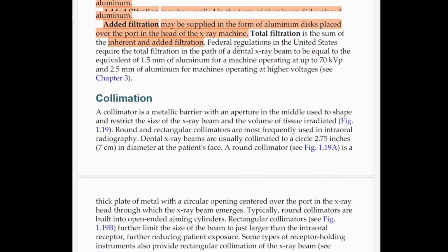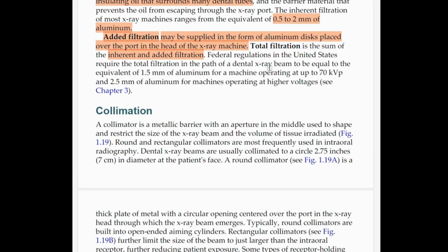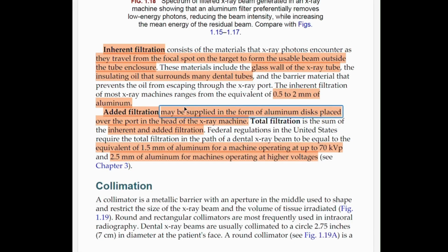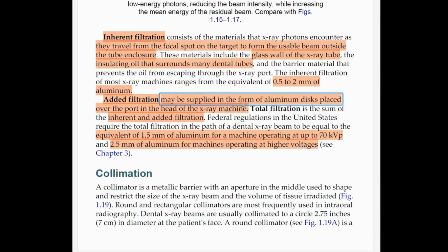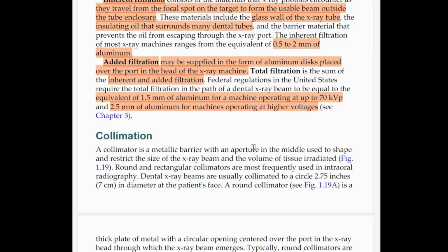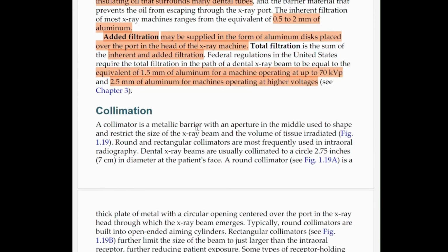Collimation. And yeah, one more point. In your added filtration, you have to write the size equivalent is 1.5 mm of aluminium for a machine that is operating at 70 kVp and 2.5 mm aluminium for a higher voltage. So in your inherent filtration, 0.5 to 2 mm in most X-ray machines; in your added filtration, if it is up to 70 kilovolt, then you have to use 1.5 mm of aluminium, and if it is higher than that, then you have to use 2.5 mm.